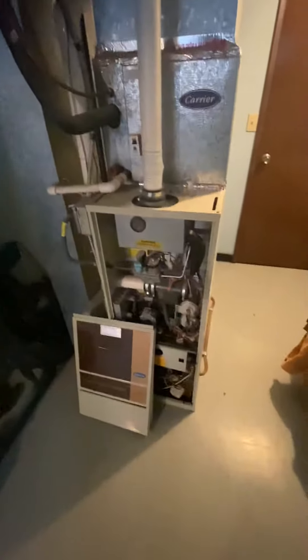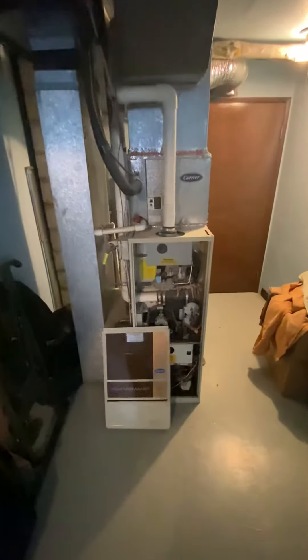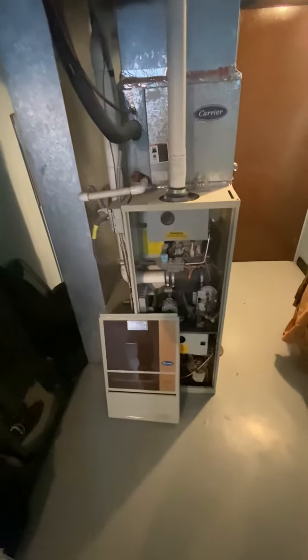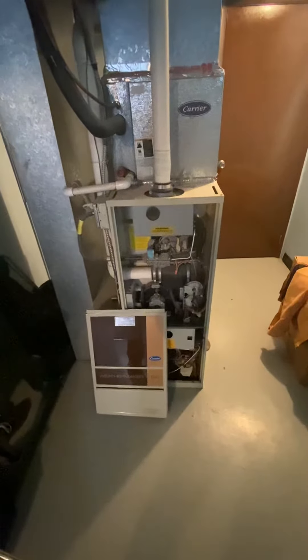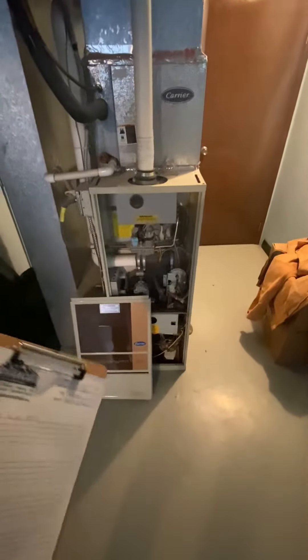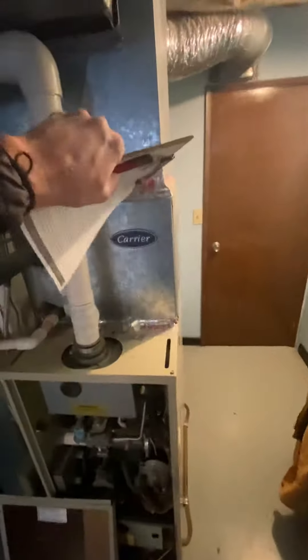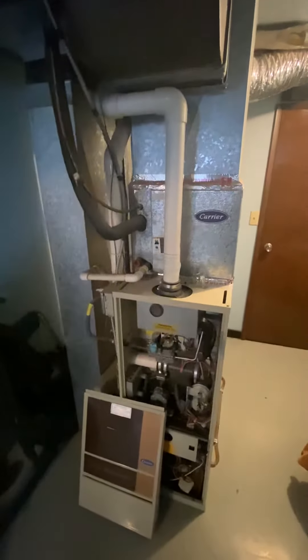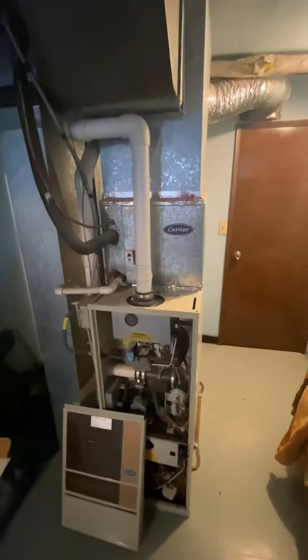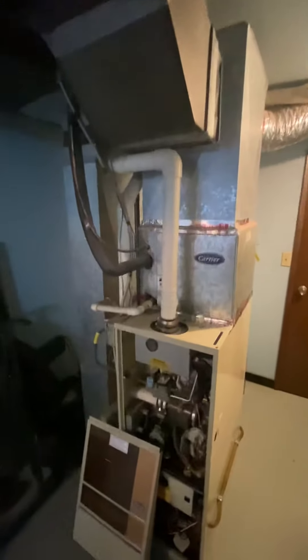I'm at the home of Miguel Garcia taking a look at his furnace. It's a 33-year-old Carrier unit, 63,000 BTU, 17 inches wide. From the ground to the top of the coil is 61 inches, and from there up to the bottom of the ductwork is 72 inches. It does have AC and it's a 90% efficiency unit.